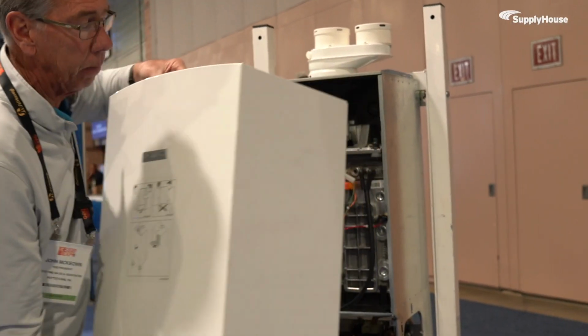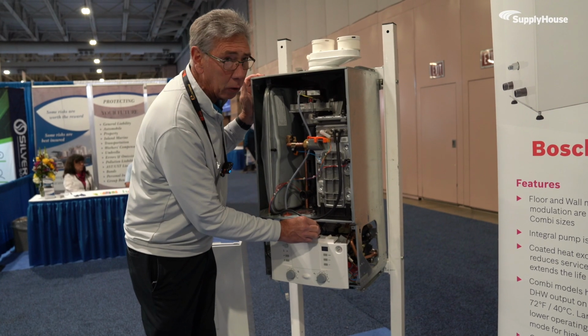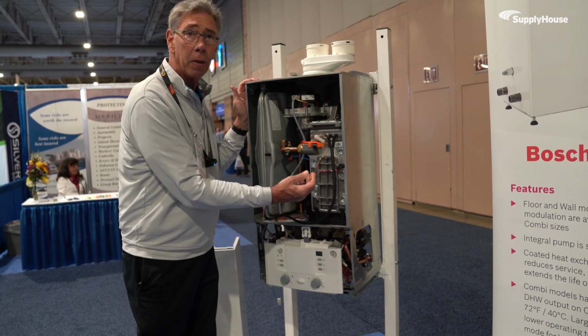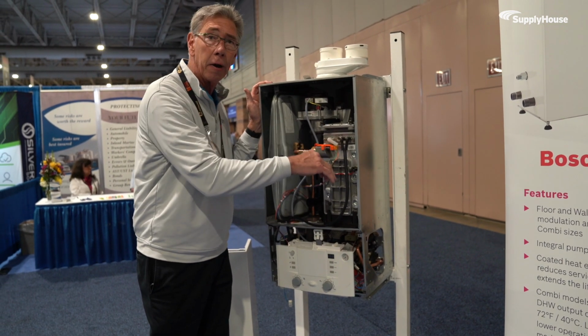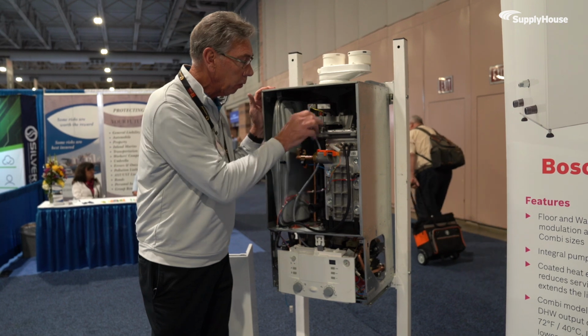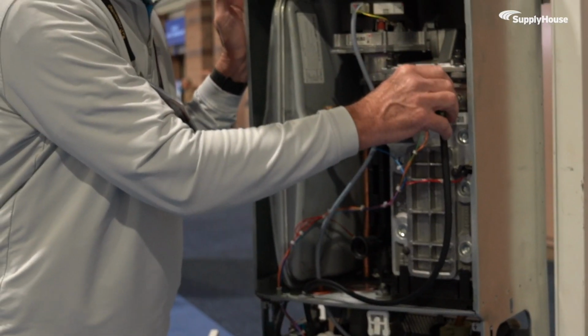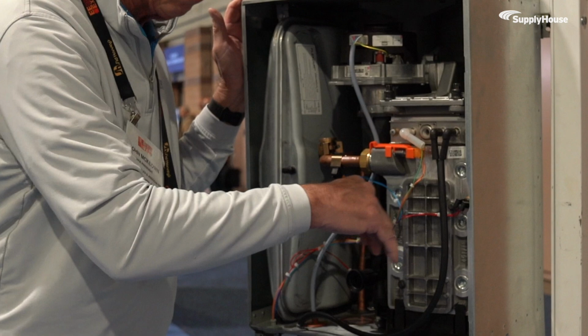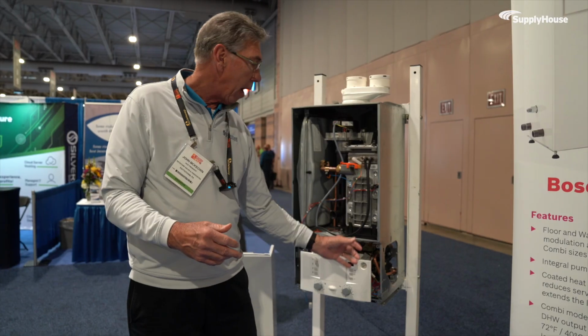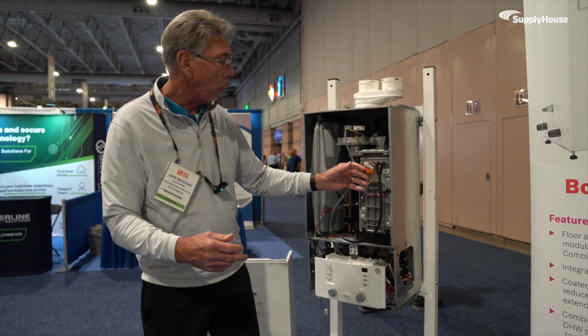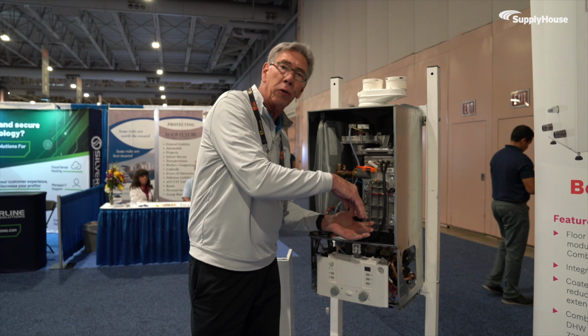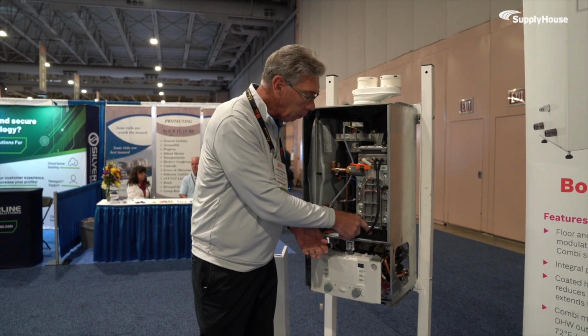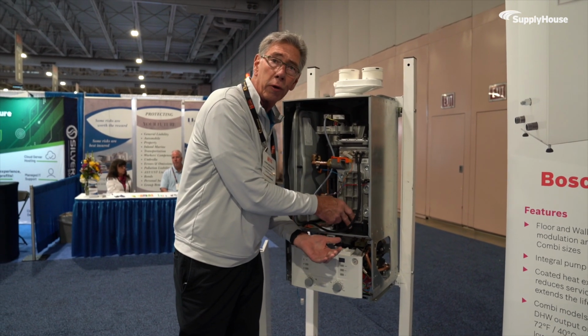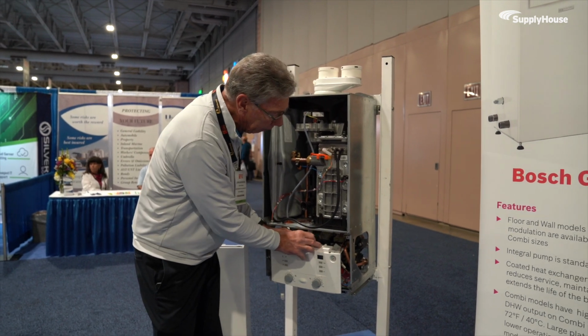Inside this unit, basically we're bringing the water back up through the unit like this, a counterflow design, and we downfire here. We've got our gas-air mixture going through here, bringing it up, spark ignition, flame rod, and the flue gas is scrubbing. Our whole idea with condensing technology on this unit is to bring in the coolest return water temperature, and we pump it up this way and let the flue gas go down.